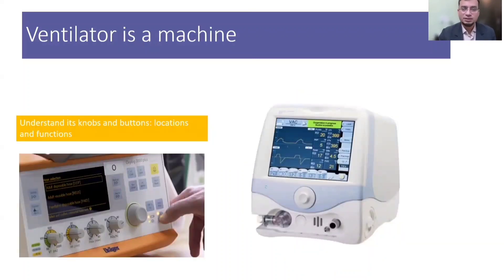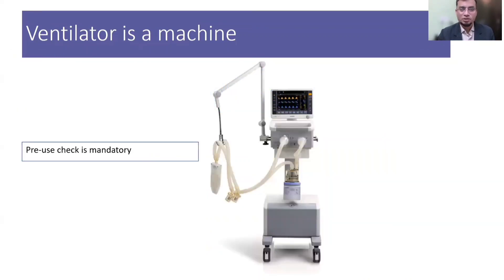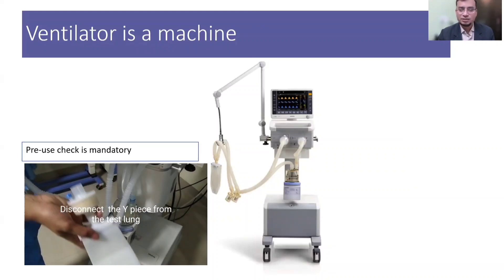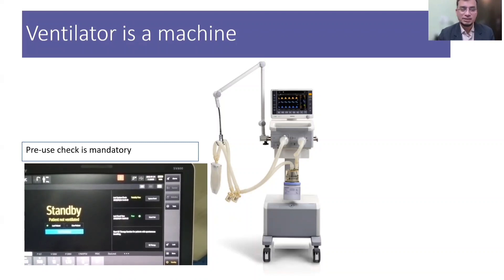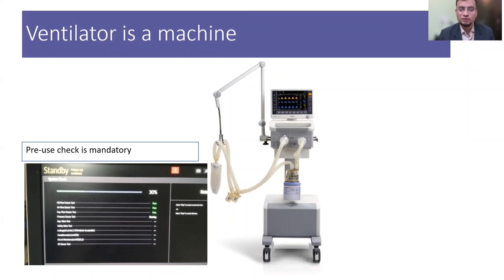The ventilator is a life support machine which assists in breathing. Because it interacts with the patient, we must understand the locations and functions of various knobs and buttons properly. Everyone who uses the ventilator on a patient must go through the user manual provided by the manufacturer. We should connect the circuit and humidifier and check the machine on a test lung. This test is called a pre-use check, designed to check the integrity of the ventilator circuit, test for leaks, and verify the functioning of various components including the humidifier system.